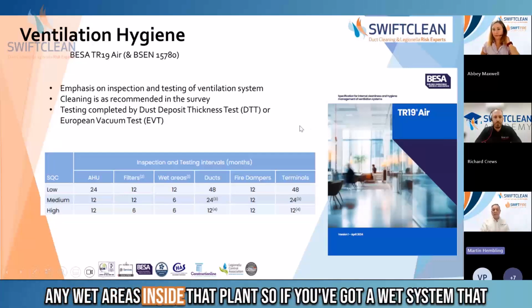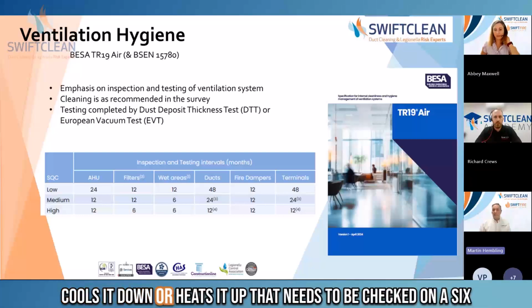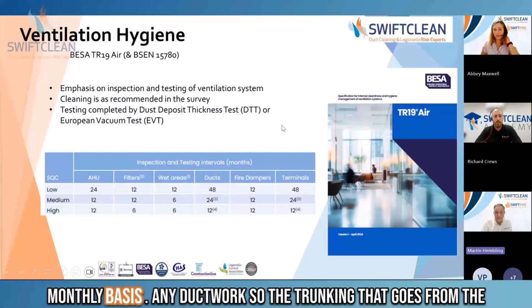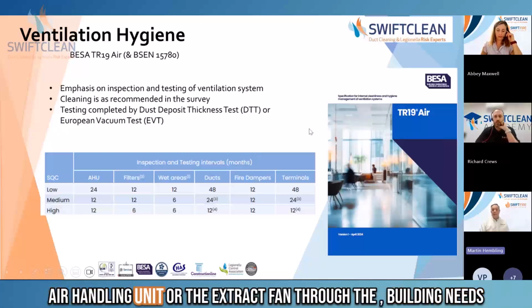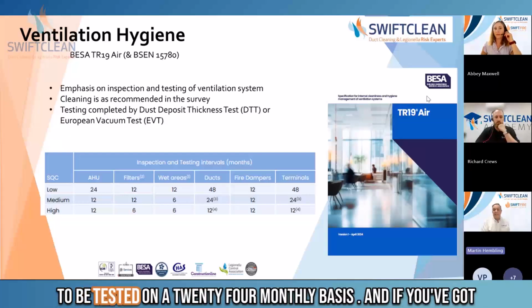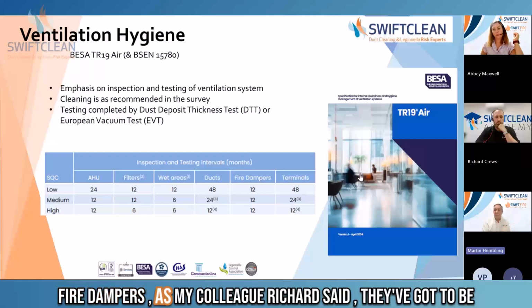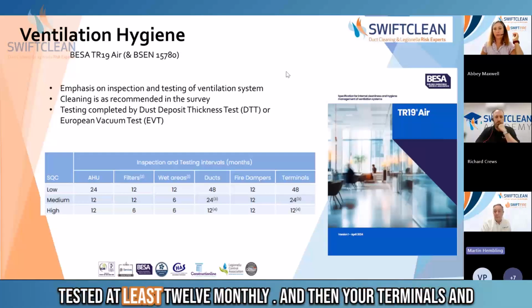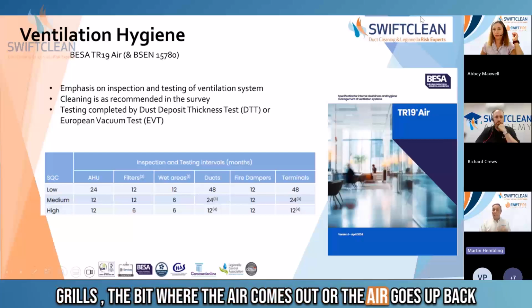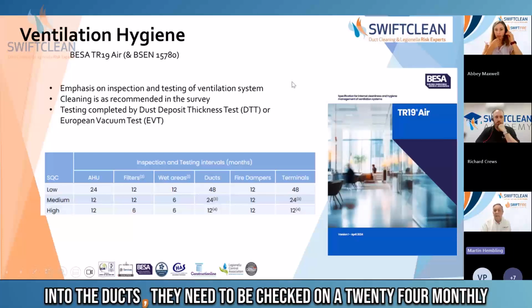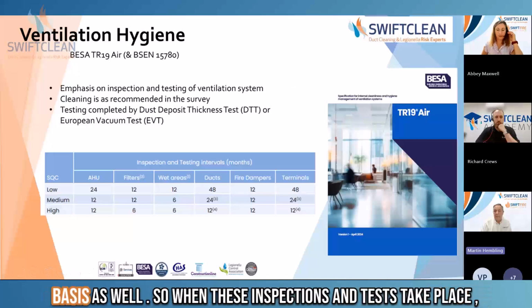Any wet areas inside that plant, so if you've got a wet system that cools it down or heats it up, that needs to be checked on a 6 monthly basis. Any ductwork, so the trunking that goes from the air handling unit or the extract fan through the building, needs to be tested on a 24 monthly basis. And if you've got fire dampers, as my colleague Richard said, they've got to be tested at least 12 monthly. And then your terminals and grills, the bit where the air comes out or the air goes up back into the ducts, they need to be checked on a 24 monthly basis as well.